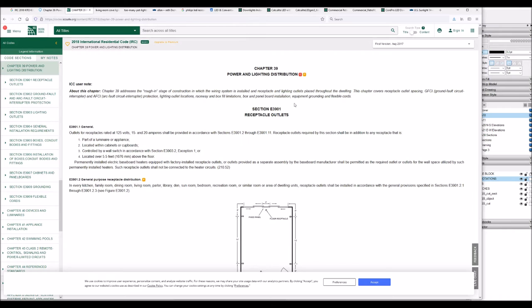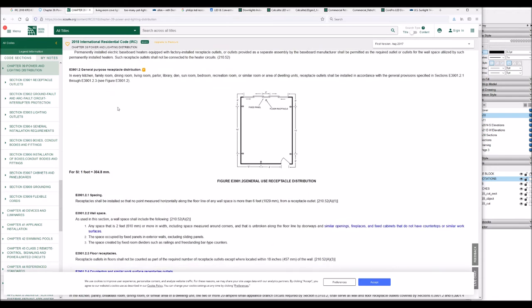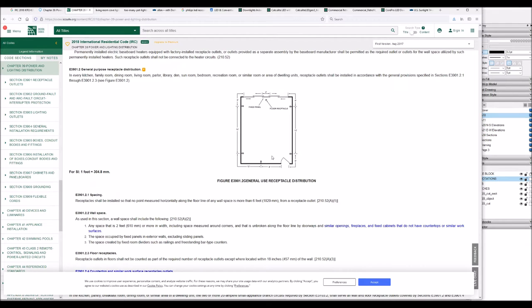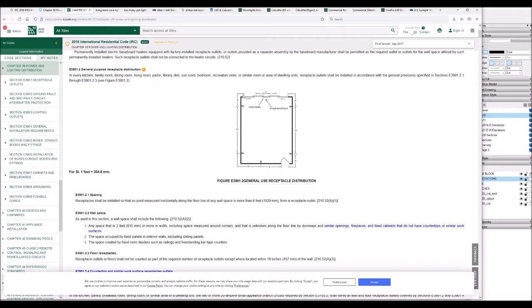Regarding plugs, receptacle outlets, basically it says that you need to have plugs every 12 feet. That's what it comes down to. You look at this picture here. It says you have to be no more than six feet from a plug. So that adds up: six feet in each direction gives you 12 feet. If you have a very short piece of wall, something under two feet in width that's interrupted on both sides, you don't need a plug in that piece of wall. But if it's anything two feet or wider, you need to count it towards the six feet. So you wrap around the corners when you do your six feet.